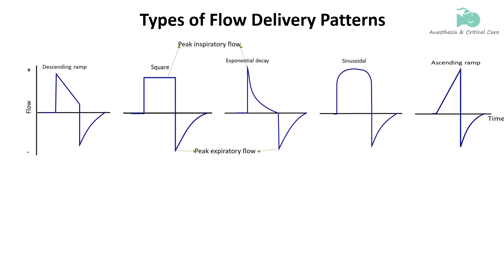Flow rate plays a crucial role in determining how gas is delivered to the lungs during mechanical ventilation. Ventilators can deliver gas in different flow waveforms, represented on the ventilator as a flow-time waveform. When flow is directed into the lungs during inspiration, it is plotted as a positive value. When the patient exhales, flow reverses direction and is plotted as a negative value. The expiratory flow is usually passive and the same for all waveform types, with a gradual decline to zero before the next breath.